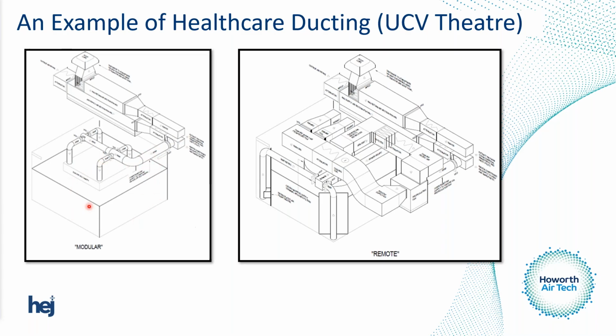So that can be used for the air change rate calculation, which I'm going to touch on later on with you all. And then if we had adequate length from there to the intake section here where it comes onto the UCV, we could take a traverse there, a traverse there, a traverse there, and a traverse there, and then we could get a total volume to each quarter to balance the ventilation system to the UCV too. You can see that there's VCDs at each leg, so the system can be quite easily worked on, balanced and assessed from a clinical and an engineering point of view.